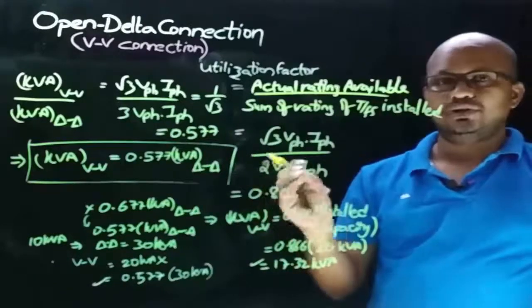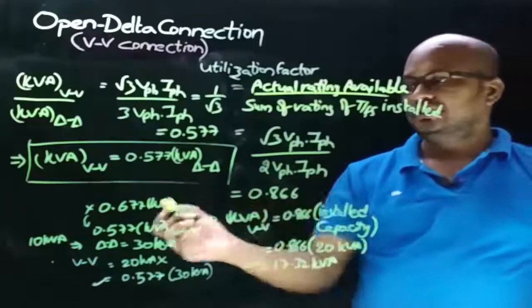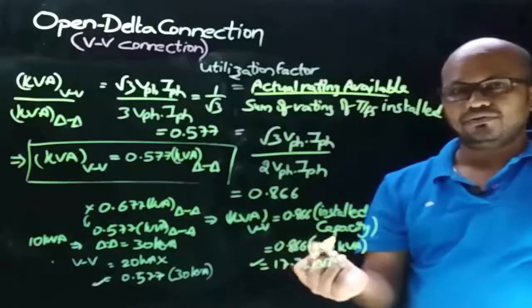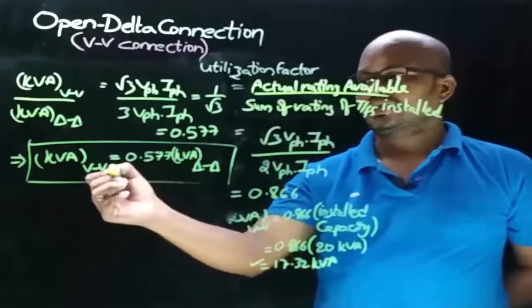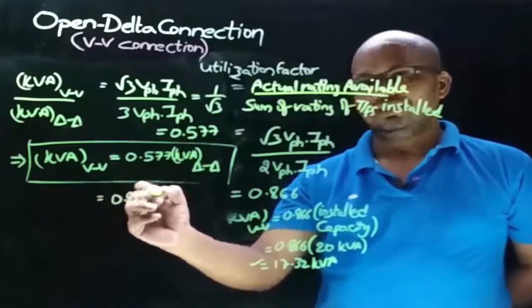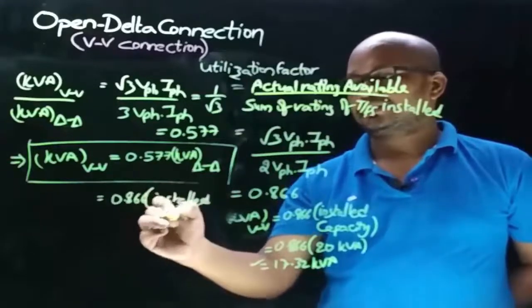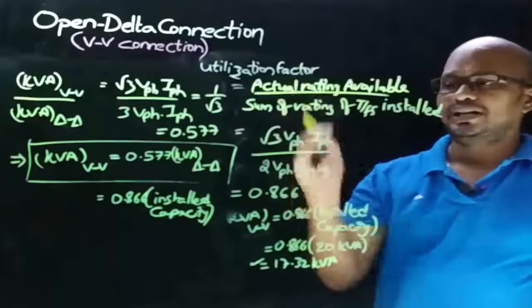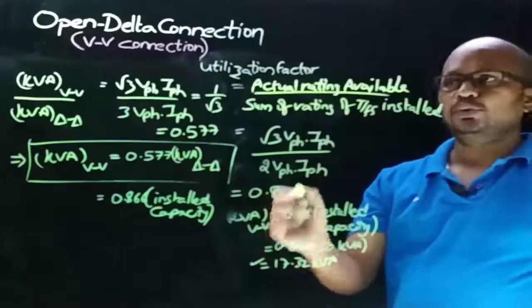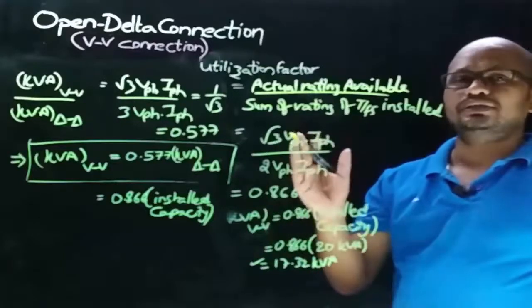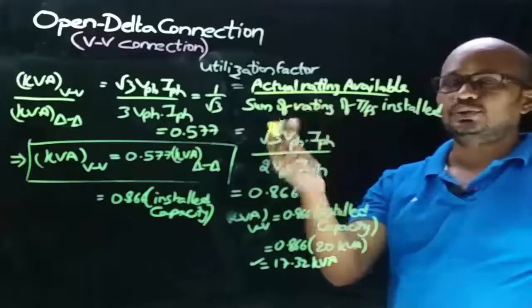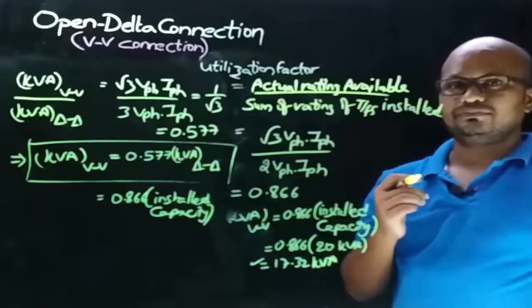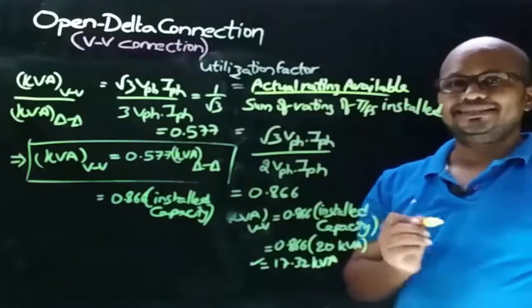So the KVA rating of open delta connection equals 0.866 times the installed capacity. This means the power delivered to the load can be taken as 57.7% of delta-delta connection rating, or 86.6% of the installed capacity. The utilization factor for open delta connection is 0.866, which is a poor utilization factor compared to Scott connection. Therefore, to transfer three-phase power with two transformers, Scott connection is preferred because it has a better utilization factor of 0.92.